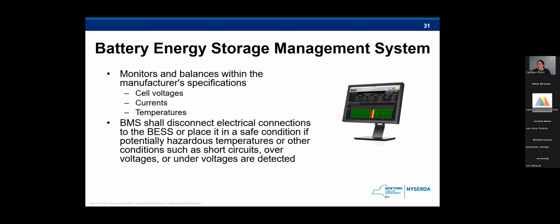So here we have the battery energy storage management system requirement. As I've stated a few times tonight, this is considered an instrumental safety feature of the energy storage system, and is considered the eyes and the ears of the battery system's health. The device is constantly monitoring the state of health of the system. If the battery management system were to fail, that would definitely lose a major safety feature. And this is probably the most important feature of the system in its effort to prevent thermal runaway, as it's able to detect anything that's abnormal and able to isolate those cells or modules.